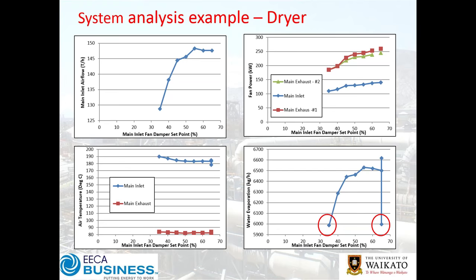There were some interesting effects on temperature going into the dryer. Crucially, there was also a substantial drop in the exhaust fans — in excess of 100 kilowatts in power savings. For an around-the-clock plant, that's substantial. The irony of course is that not only could you get those power savings, you could also get an increase in capacity.